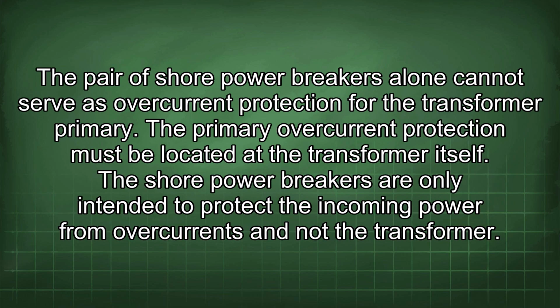The pair of shore power breakers alone cannot serve as overcurrent protection for the transformer primary. The primary overcurrent protection must be located at the transformer itself. The shore power breakers are only intended to protect the incoming power from overcurrents and not the transformer.